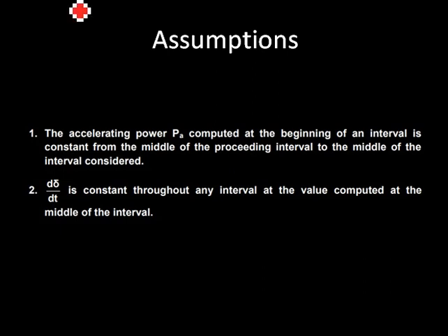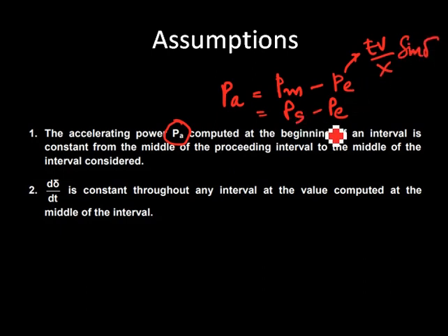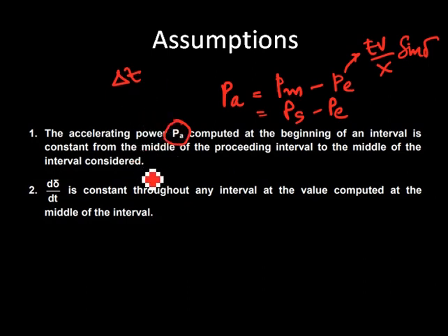We move forward with some assumptions. The first is the accelerating power Pa. For a generator, Pa equals Pm minus Pe — mechanical power minus electrical output. Pe is given by EV/X times sine delta. The entire process is divided into time intervals delta-t, and at each interval you calculate accelerating power and d(delta)/dt. The accelerating power computed at the beginning of the interval is assumed constant.